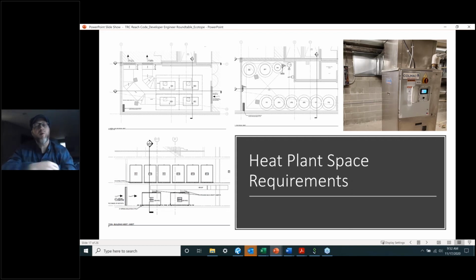What we've found putting heat pumps in the garage is about a half a COP increase in performance with the 134A devices—these are the Colmac heat pumps. One thing I'd say is we typically set these up in a room, duct the discharge air out, and pull makeup air in through a louver into that mechanical room. These are just using the buffered space in a below grade parking garage. We've never seen the parking garages get below 40 degrees, which happens to be about the limit of most 134A equipment. Some equipment can operate lower than 40-degree entering air, but that works out okay on these plants. We've got monitoring on several plants in Seattle in this configuration, and with Colmac we're getting COPs of about 2.7 on the annual.